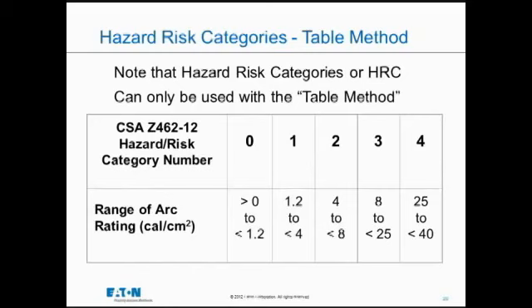So there has been a distinction, and the reason for that is there is no evaluation of risk when you're doing energy analysis. There is no analysis of risk. We're just calculating out the hazard based on the parameters, the voltage, the current, the distance, and the time. We're not evaluating the risk. You know, is it more risky to open up a bolted cover, or is it less risky, let's say, to open a hinge door? This is where risk analysis comes into the workplace. What am I doing? And is it more risky to do something? And that's built into this table method. So it's the only place where we can use the word HRC, because that includes the word risk.